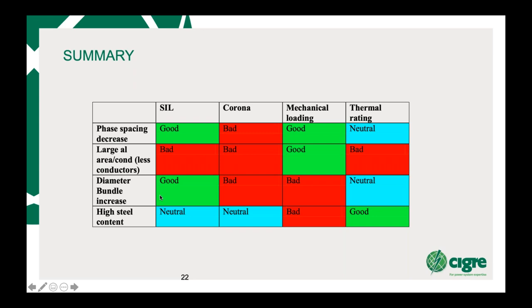For diameter, if you're increasing the bundle diameter, the SIL is good, up to a point. So here we're increasing the bundle diameter. SIL is good, corona is bad, as we said, because you need to actually reduce the bundle diameter to improve your corona performance. So the SIL is good, and you can find that in the examples in Brazil, where they use very large bundles, 1 meter or 1.2 meters between subconductors. And that gives you a very good, or what is called a high SIL line.